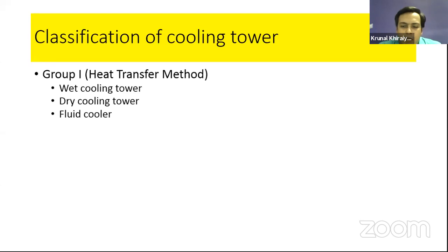Dry cooling tower means no evaporation occurs, and we still achieve the cooling of water. The third one is the fluid cooler. I want to say that dry cooling towers and fluid coolers are special applications used in chemical industries. In chemical industries, we need to cool some special kinds of fluids, such as acids, sometimes substances which are not exactly water. Once a chemical evaporates, it goes into the environment, and it has a hazardous effect.